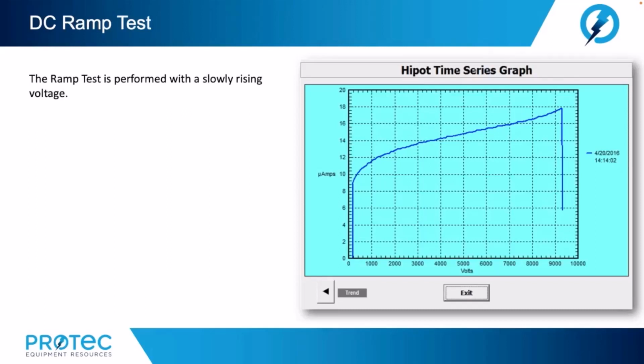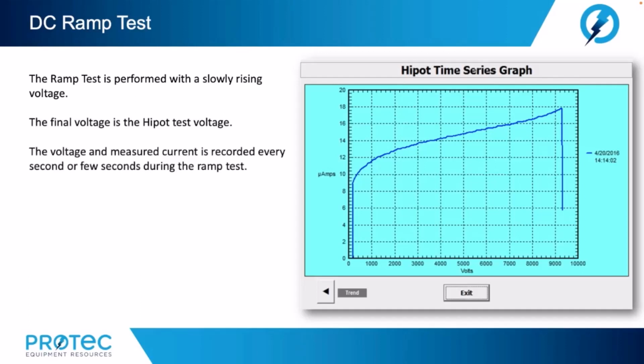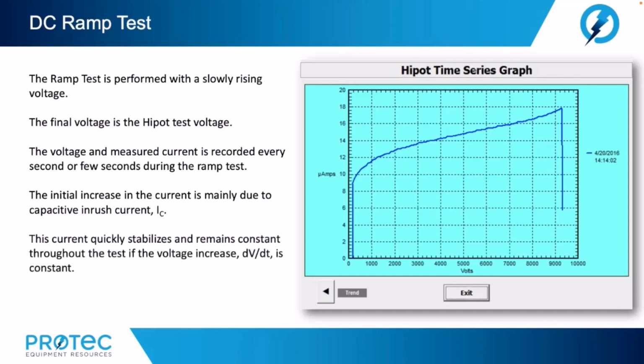Let's take a look at the high potential test known as the DC ramp test. The ramp test is performed with a slowly rising voltage. The final voltage is the high pot test voltage. The voltage and measured current are recorded every second or few seconds during the ramp test. The initial increase in the current is mainly due to capacitive inrush current. This current quickly stabilizes and remains constant throughout the test if the voltage increase, delta V divided by delta T, is constant. The capacitive current will equal the winding capacitance times the change in voltage divided by the change in time.